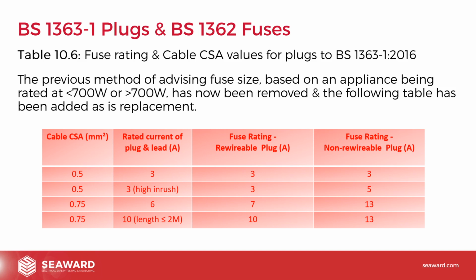And this is obviously why testing new equipment is important, because you can start a benchmark. You can see what fuse was in that equipment when it was new, and then make sure over time that that rating is always used with that particular piece of equipment. So it is a bit of a change to the guidance, the way of doing it, because we had quite a sort of blunt instrument before with the 700 watts greater than or less than guidance, whereas now all they've done is include the table from the standards, and this is the standards that the manufacturers would be looking at when they're picking the fuse sizes. So hopefully it will align with that, but I'm sure there's probably going to be a few anomalies and a few bits of head scratching that go into that as we move forward.